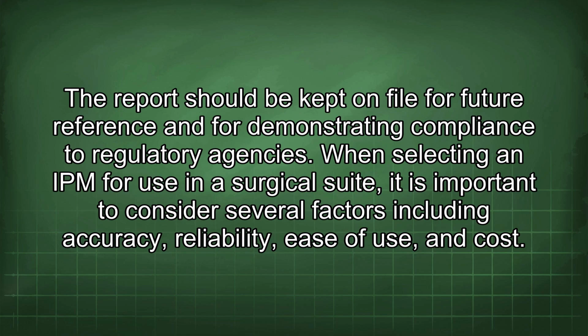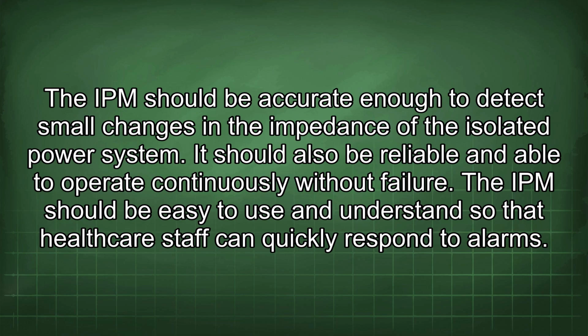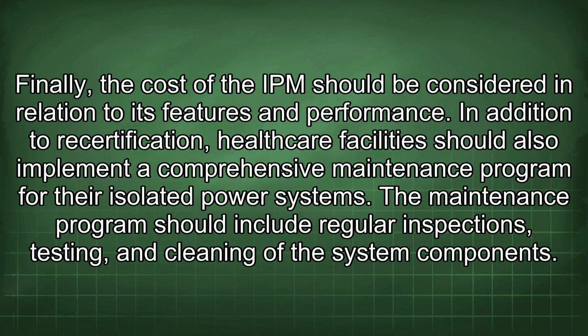When selecting an IPM for use in a surgical suite, it is important to consider several factors, including accuracy, reliability, ease of use, and cost. The IPM should be accurate enough to detect small changes in the impedance of the isolated power system. It should also be reliable and able to operate continuously without failure. The IPM should be easy to use and understand so that healthcare staff can quickly respond to alarms. Finally, the cost of the IPM should be considered in relation to its features and performance.